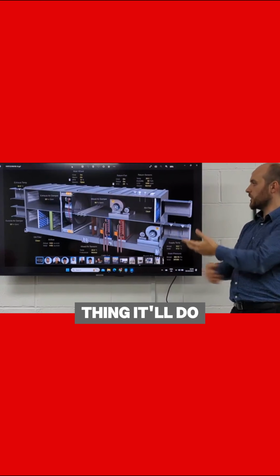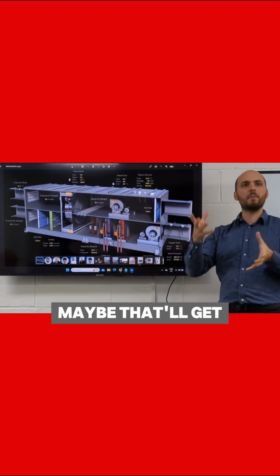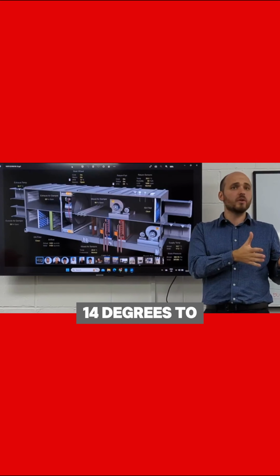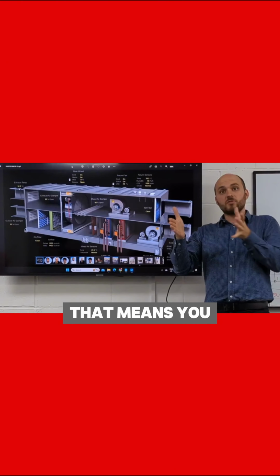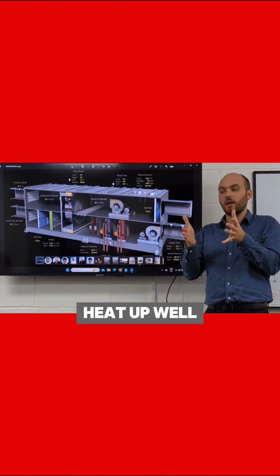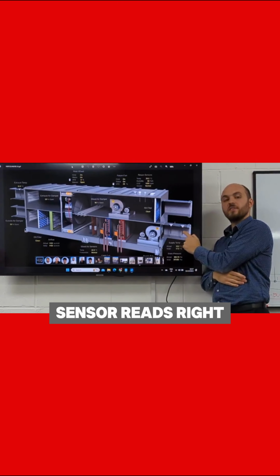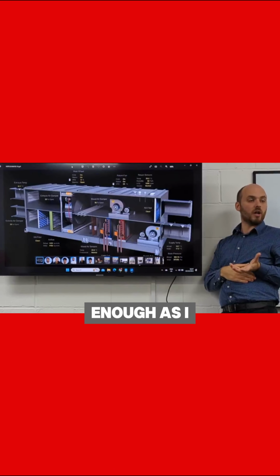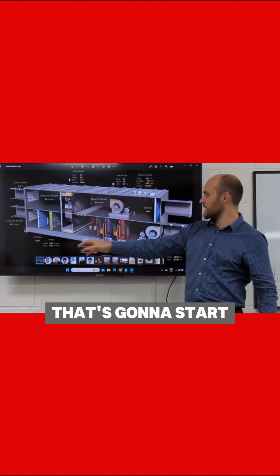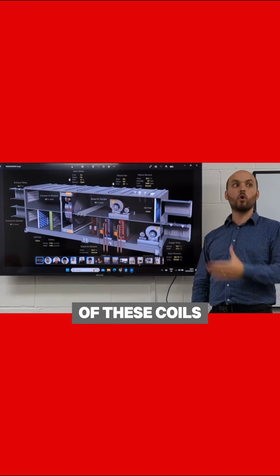So the first thing it'll do is it'll put the thermal wheel on. Maybe that'll get the air from 14 degrees to 18 degrees, right? That means you've still got 3-4 degrees to heat up. Well, in that case, when this temperature sensor reads, right, I'm not hot enough as I need to be to reach set point, that's going to start turning on one of these coils.